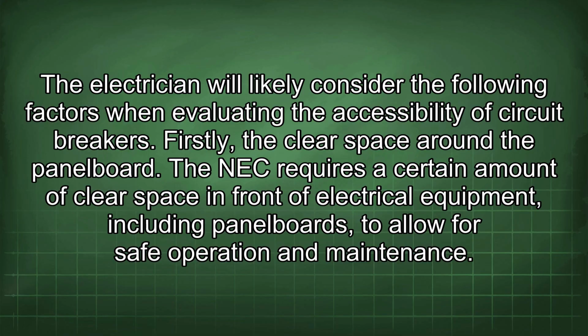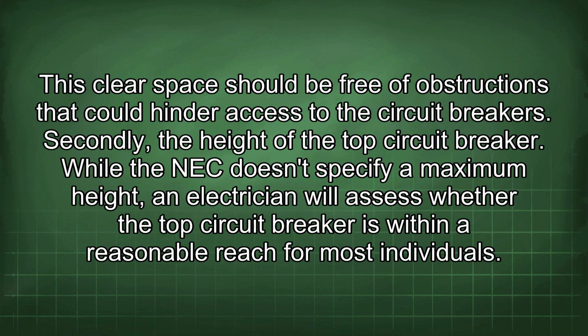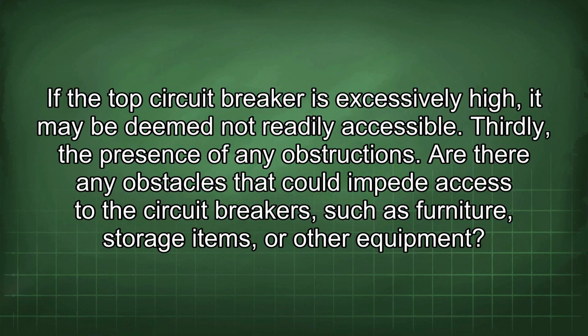Firstly, the clear space around the panel board. The NEC requires a certain amount of clear space in front of electrical equipment, including panel boards, to allow for safe operation and maintenance. This clear space should be free of obstructions that could hinder access to the circuit breakers. Secondly, the height of the top circuit breaker. While the NEC doesn't specify a maximum height, an electrician will assess whether the top circuit breaker is within a reasonable reach for most individuals. If the top circuit breaker is excessively high, it may be deemed not readily accessible.